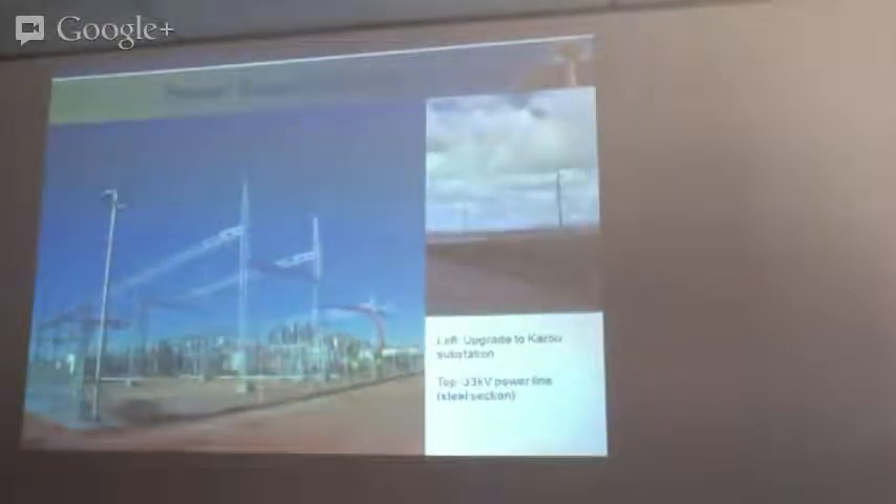At the moment we're operating the power line at 22 kV capacity and we'll switch over to 33 kV capacity in the next month or two. As mentioned, the cap on the power supply to site is approximately 5 MVA at this stage, so there will be a cap for SKA Phase 1. The power line runs about 30 kilometers from site — from Carnarvon to 30 kilometers outside the site we have a wooden pole structure, and then we change over to a steel pole structure in terms of RF interference protection, so we don't want sparking on the line causing interference with the dishes.